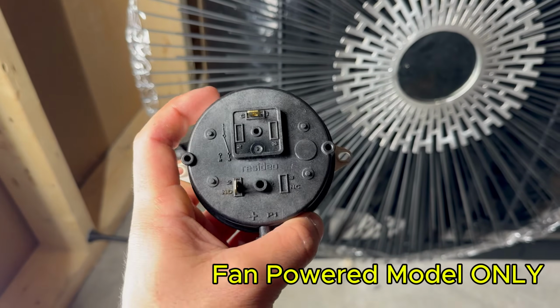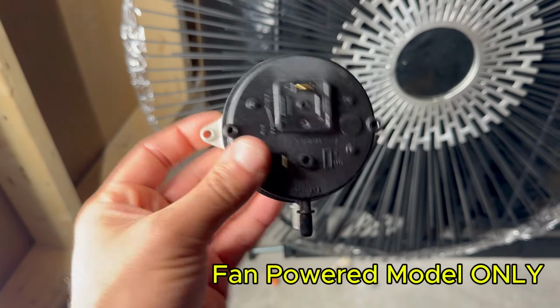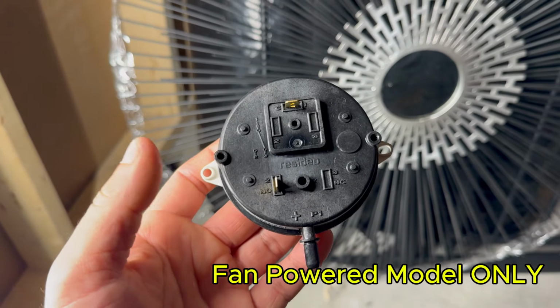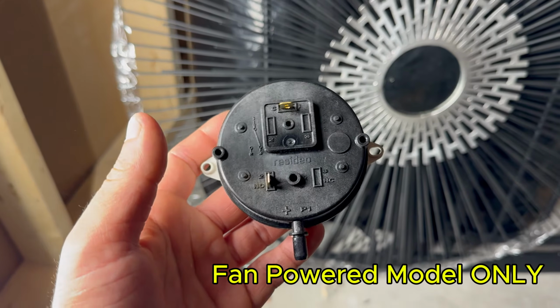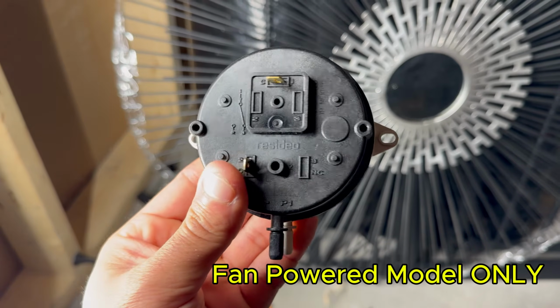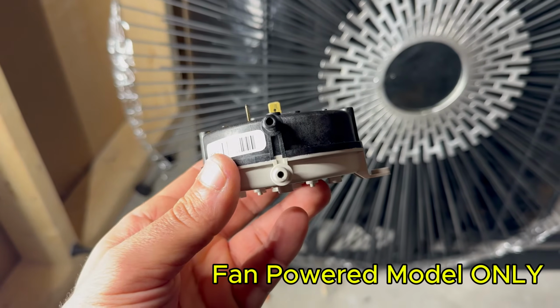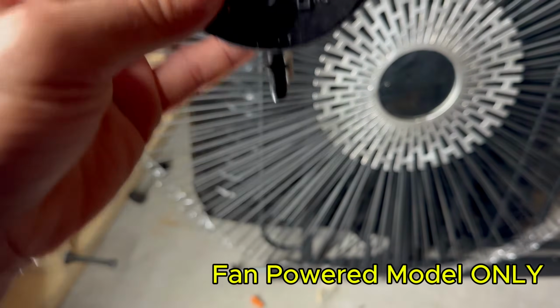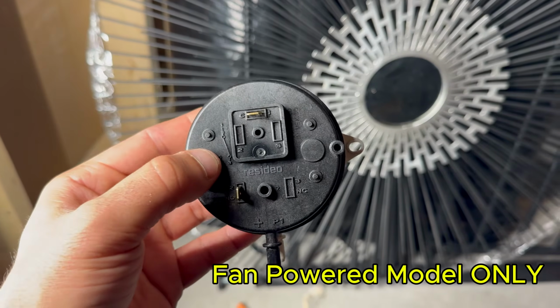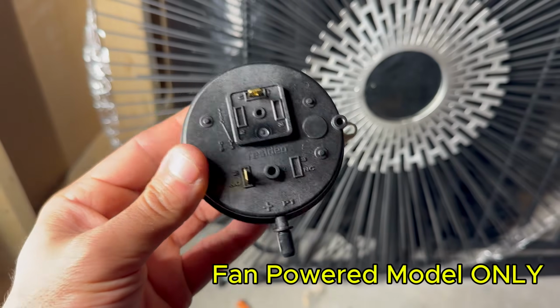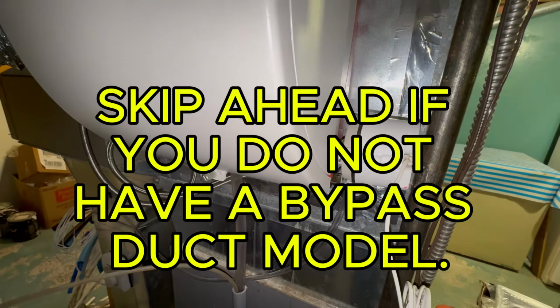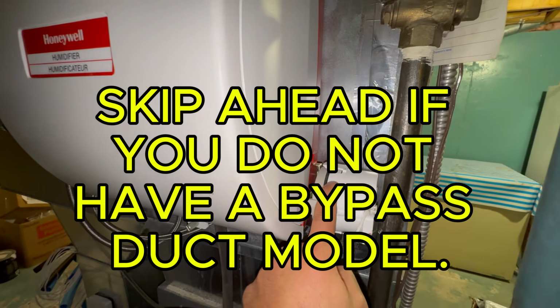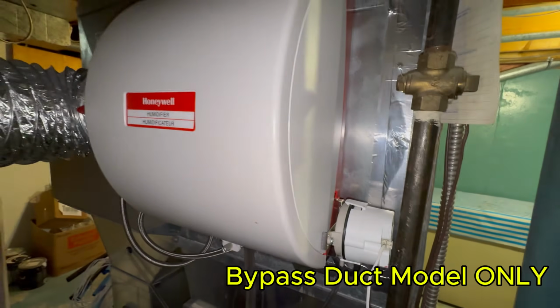So what we're going to do is mount this using 2 sheet metal screws on the return side of our ductwork. There's 2 holes for sheet metal screws, and what you're going to do is have these 2 nipples pointing downwards and the black side facing you with the terminal connections facing you. Skip ahead. When you're working with the pressure switch, it's a little bit easier on this model.